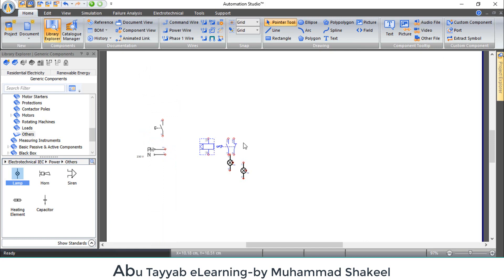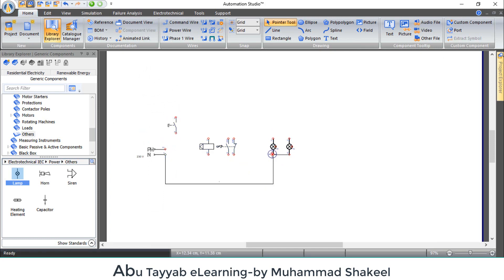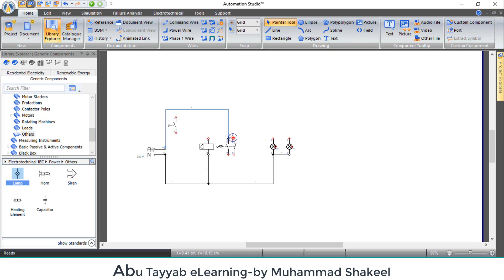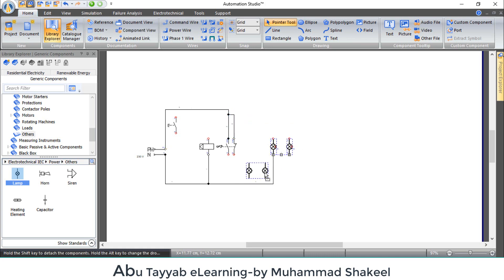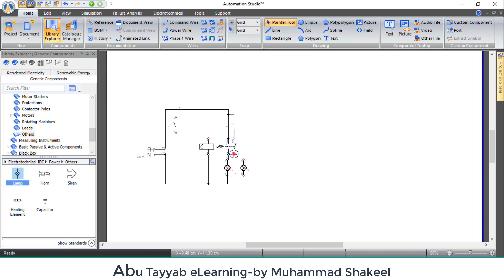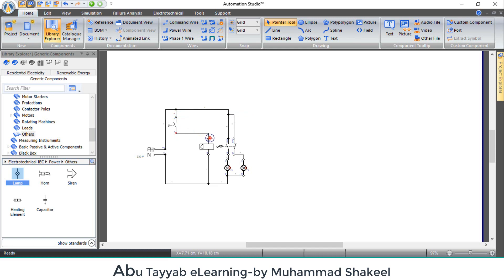Arrange the components and make connections. Connect neutral to the coil and lamps. Connect phase to both lamps through the relay contacts. One lamp will be connected with the normally open contact and the other will connect to the normally closed contact. And connect the relay coil through the push button.